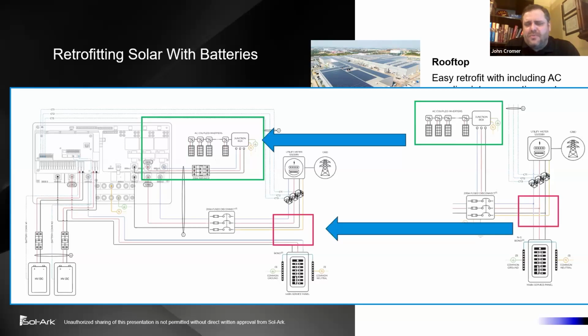There is a little bit of nuance with AC coupling, which comes into what is the size between the solar array and the battery inverter. What it boils down to is, if you want to use the solar array for backup power, then the solar array needs to be the same size, more or less, as the battery inverter bank. So if you have, let's say, a 125 kilowatt SMA Sunny Tripower on 480 volt service, you'd want two Sol-Ark 60Ks to be roughly equivalent in size. You don't want the AC coupled solar to be much larger than the nameplate capacity of the Sol-Ark inverter. Now, if it's a non-backup application, that's a bit of a different story.